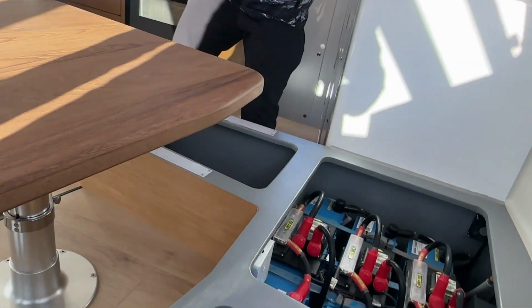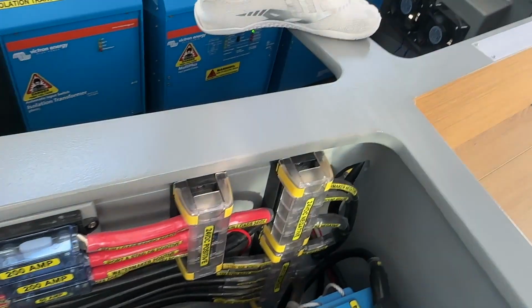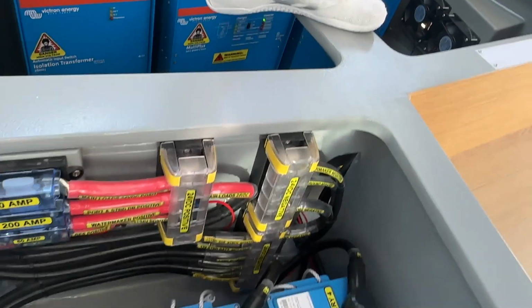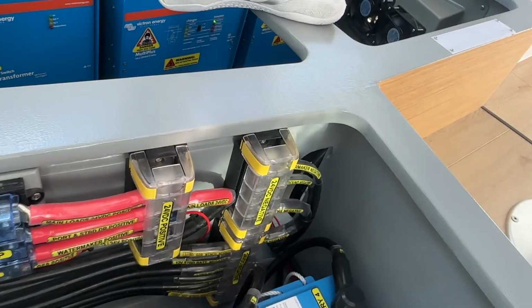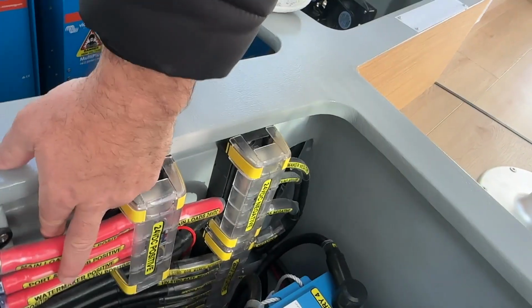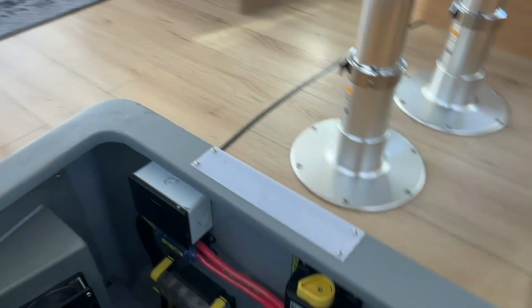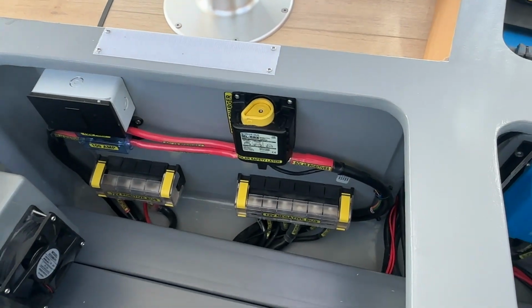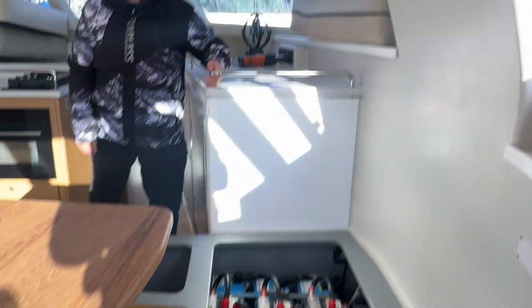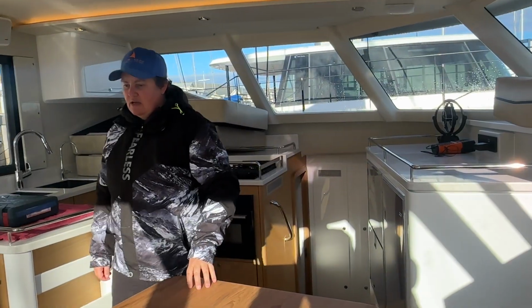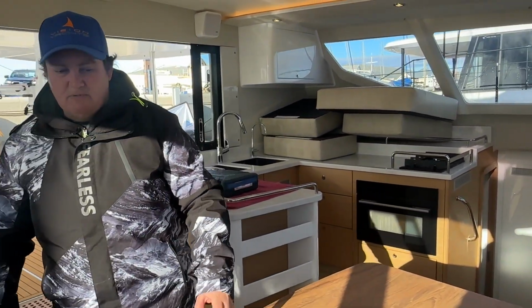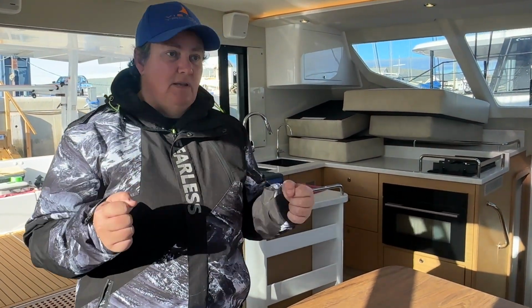Okay, so we'd also check these fuses and make sure everything's tight there as well? Yeah, so you can just wiggle your wires - if you find something loose, you will just torque them up a bit. That said, like I said, a cable has a memory inside of it until it has settled into its solid position. It usually takes anything between 6 to 8 months for a cable that size to sort of stabilize.